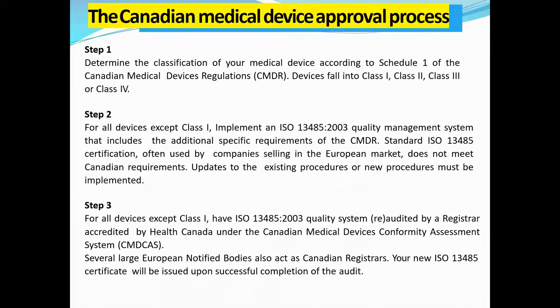That includes the additional specific requirements of the CMDR and standard ISO 13485. Always use the standards of the current year. Okay, 13485:2016 is current. This is the ISO standard which we have to use everywhere, and it has very strict requirements in the medical device industry, and it is a mandatory requirement for all manufacturers. Even in India, they ask for the ISO 13485:2016 certification. It is often used by companies selling in the European market, but it does not meet Canadian requirements. So all updates to the existing procedures or the new procedures must be implemented.